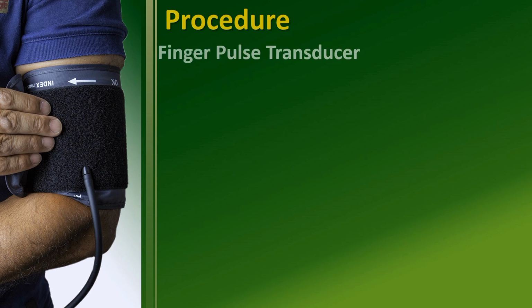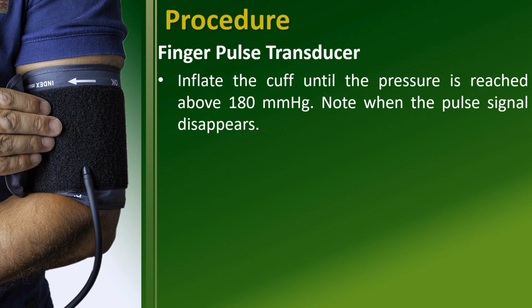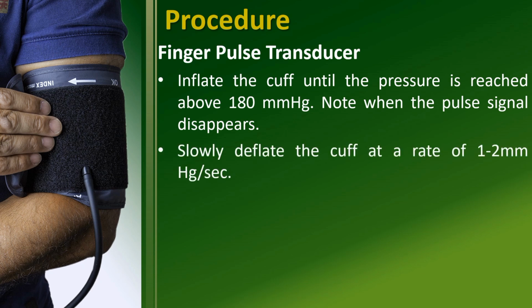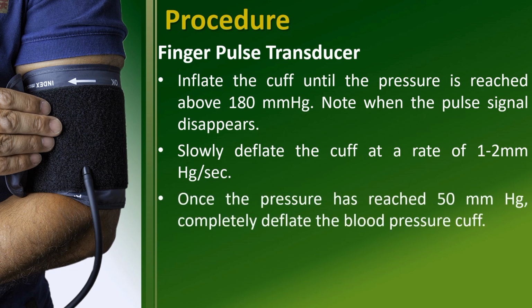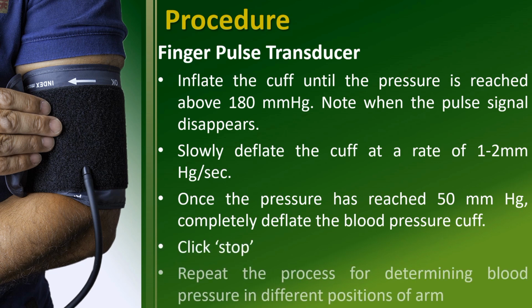After that, inflate the cuff until the pressure is reached above 180 mm mercury. Note when the pulse signal disappears, then slowly deflate the cuff at a rate of 1 to 2 mm mercury per second. Once the pressure has reached 50 mm mercury, completely deflate the blood pressure cuff, then click stop. Repeat this process for determining the blood pressure in different positions of arm, that is, when arm is bent at 90 degrees, when arm is hanging down loosely by the side, and when arm is held straight above the head.